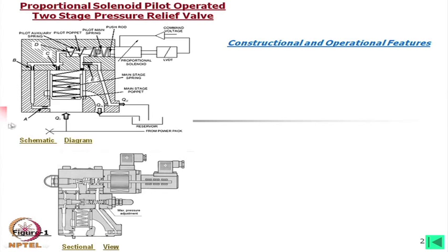Now, here again I would tell that we have seen one orifice A here, another orifice B before this pilot stage. That means, if the same oil is flowing through this pilot stage, at least there are two orifices. Apart from that, there are also some fixed resistances, fixed orifices. These orifices can be replaced, whereas this cannot be replaced.